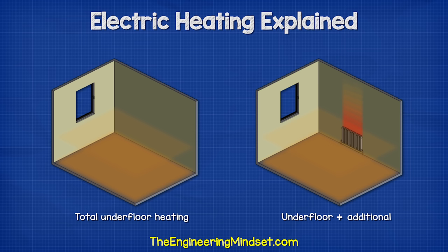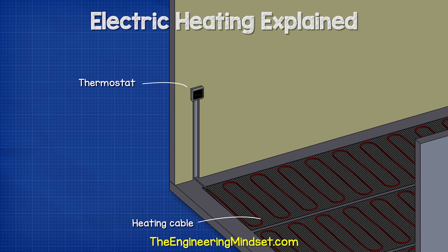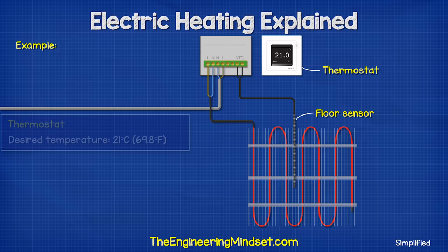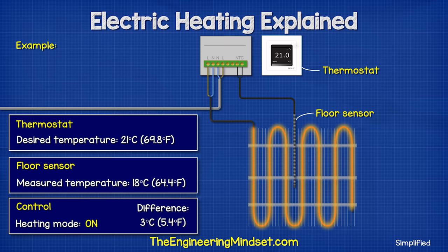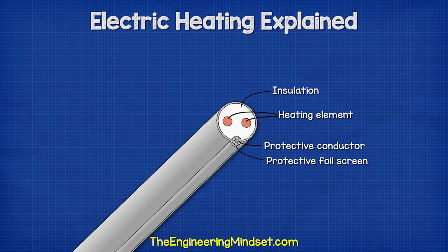If we look at a simple bathroom installation, the system is relatively simple. We just have the heating cable installed across the floor, and this is connected to the wall-mounted thermostat. We also have a temperature sensor connected from the thermostat running down to the floor. This is then all covered in an adhesive and then tiled over. The thermostat is connected to the mains power supply. When it detects that the floor temperature is lower than desired, it allows electricity to flow through the wire, which heats up the floor. The cable just has two heating elements inside - these might be solid core wires or multiple strands - covered in insulation with a thin metal protective screening and then coated with a PVC outer layer.